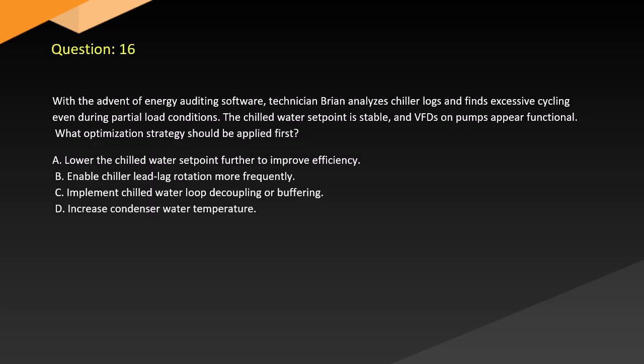Question 16. With the advent of energy auditing software, technician Brian analyzes chiller logs and finds excessive cycling even during partial load conditions. The chilled water set point is stable and VFDs on pumps appear functional. What optimization strategy should be applied first? A. Lower the chilled water set point further to improve efficiency. B. Enable chiller lead-lag rotation more frequently. C. Implement chilled water loop decoupling or buffering. D. Increase condenser water temperature.